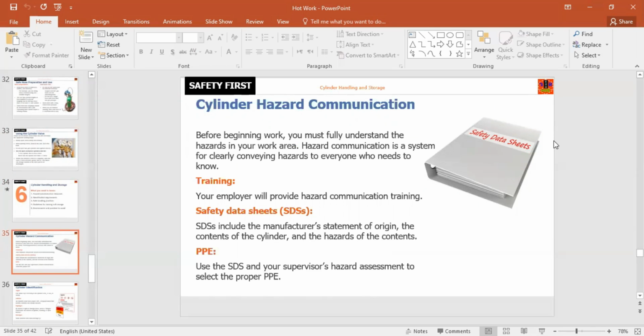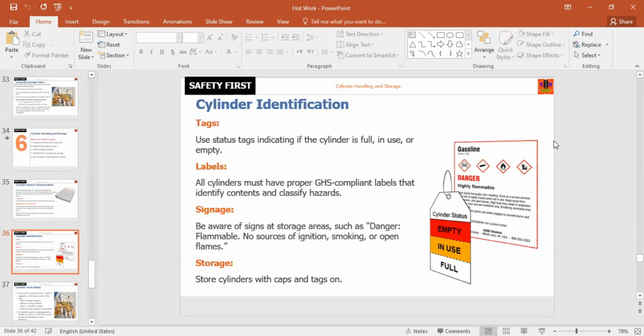Safety data sheets include the manufacturer's statement of origin, the contents of the cylinder, and the hazards of the contents. Use the SDS and your supervisor's hazard assessment to select the proper personal protective equipment. For the identification of the cylinder, use status tags indicating if the cylinder is full, in use, or empty. All cylinders must have proper GHS compliant labels that identify contents and classify hazards.